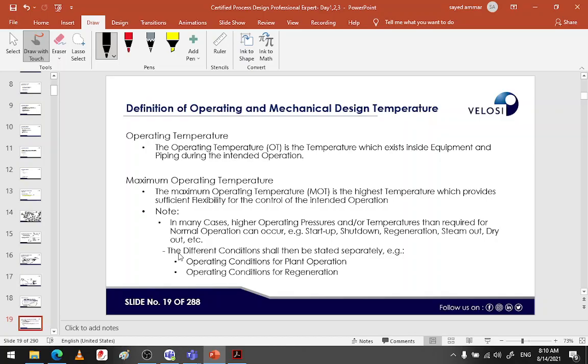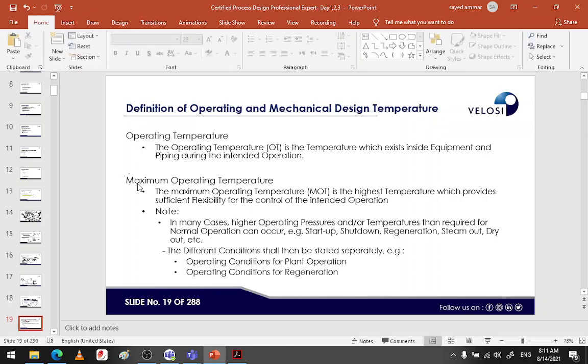Okay, operating temperature, maximum operating temperature. What is the difference between operating temperature and maximum operating temperature? The operating temperature is what we are going to see from the heat and material balance that we are going to generate today using Aspen HYSYS. Maximum operating temperature is what we should get from the code to make sure that we are selecting the right material or right equipment thickness. The maximum operating temperature is the highest temperature which provides sufficient flexibility for the control of the intended operation. Why are we afraid of this maximum operating temperature?